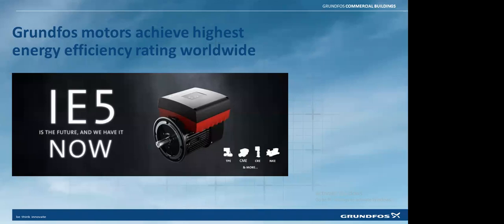So now, what we have in our latest hydropneumatic systems: we have come up with hydropneumatic systems with the IE5 motor. Earlier we used to have the terms efficiency 1 motor, efficiency 2, efficiency 3. That's a term we used earlier when discussing the efficiency class of a motor. Now the terminology has changed by the standards. It's called IE3, IE4, IE5, which are the equivalent efficiency class terms.